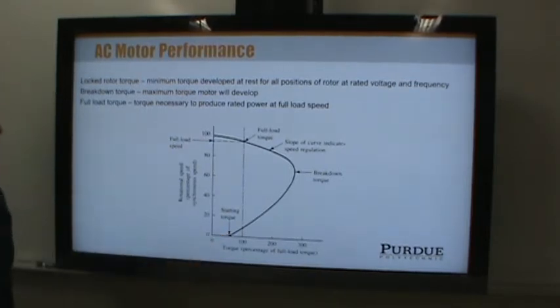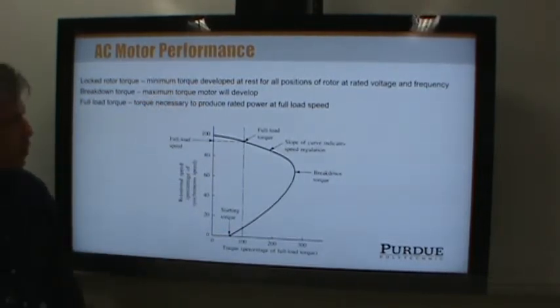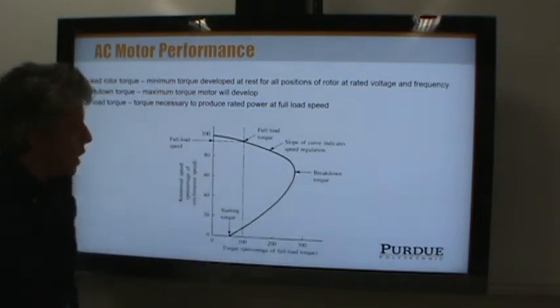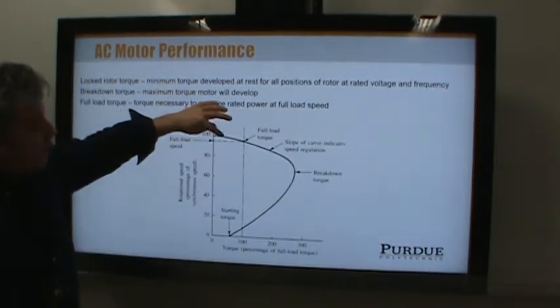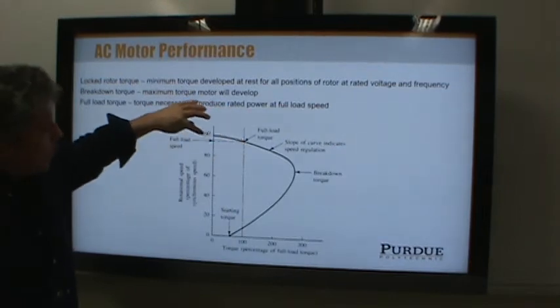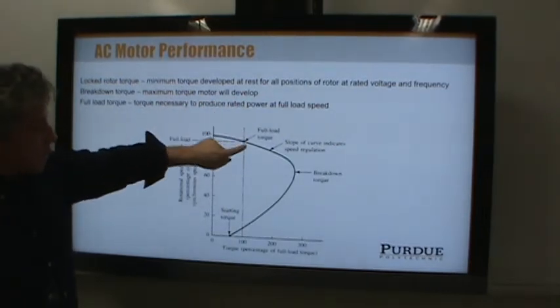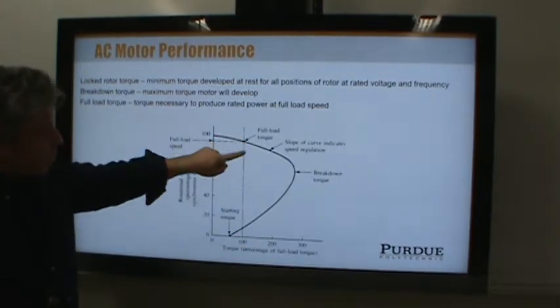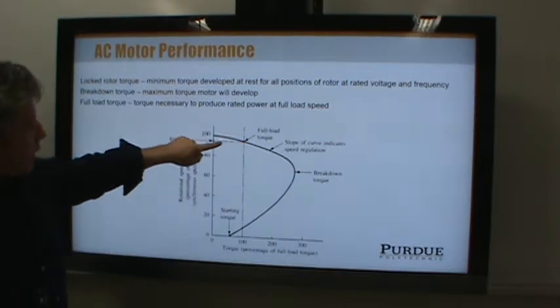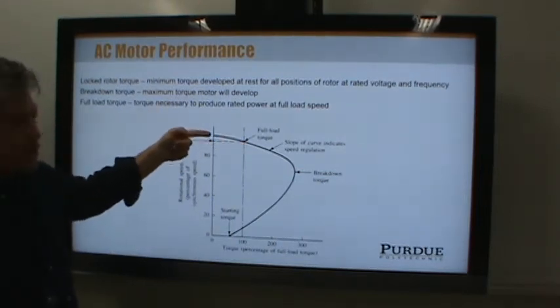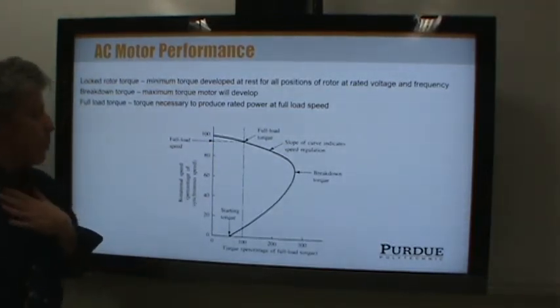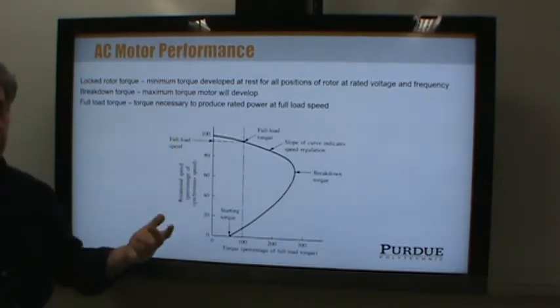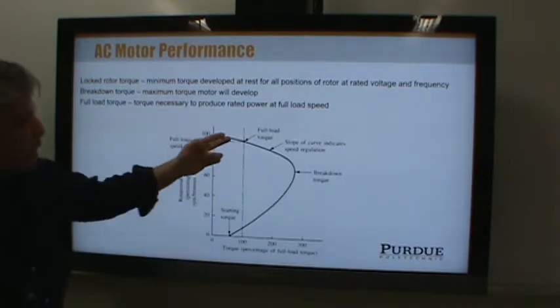The locked rotor torque, also called starting torque, is that point on the axis. The breakdown torque is the maximum torque the motor will develop. If you start the motor unloaded and reach full speed, then apply load, you reach the full load speed at the full load torque — that's the rated operating point. The speed is not quite the theoretical maximum because most AC motors slip a little bit.